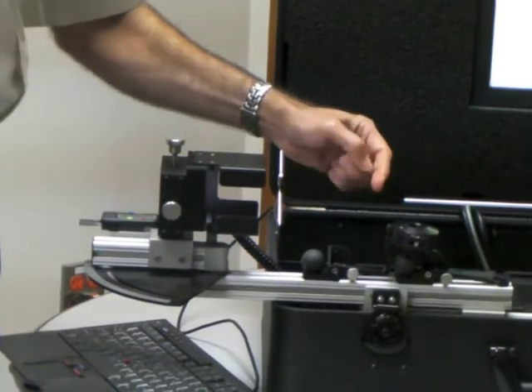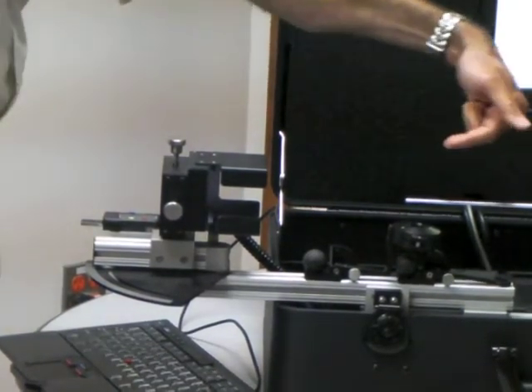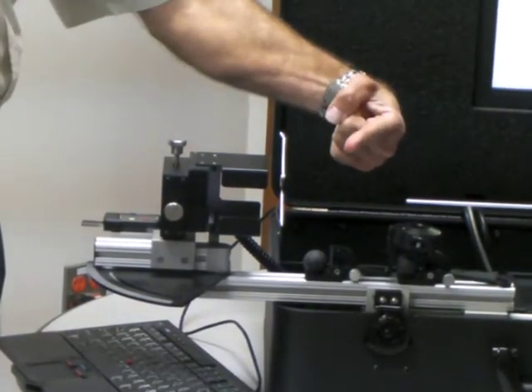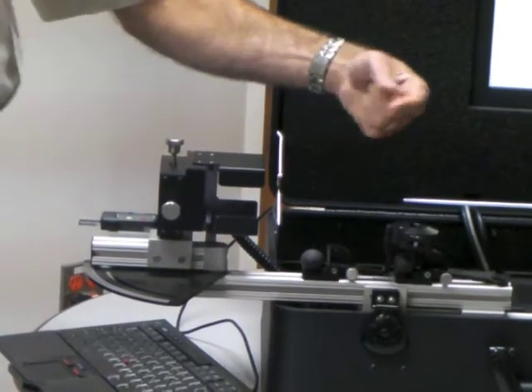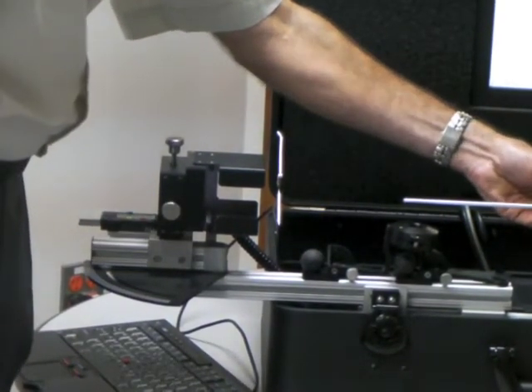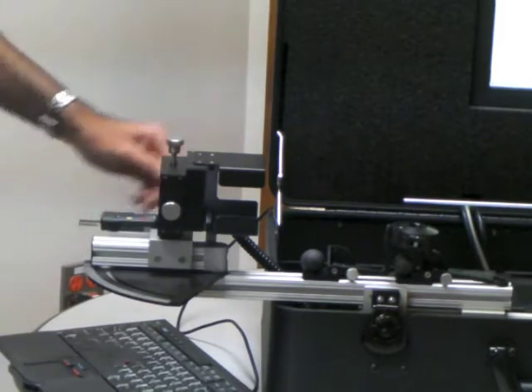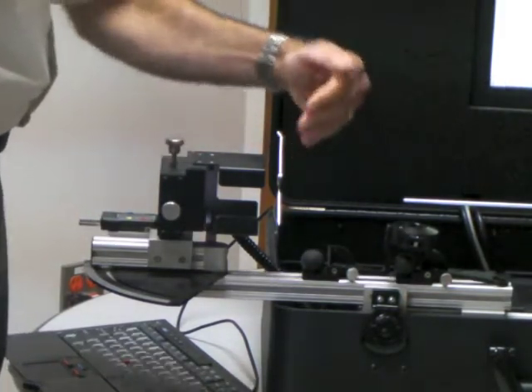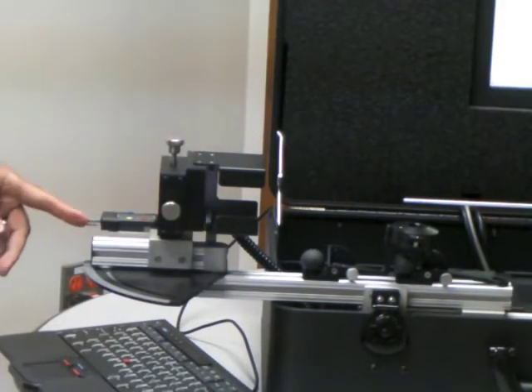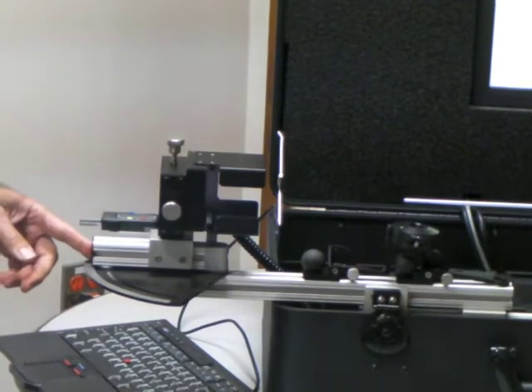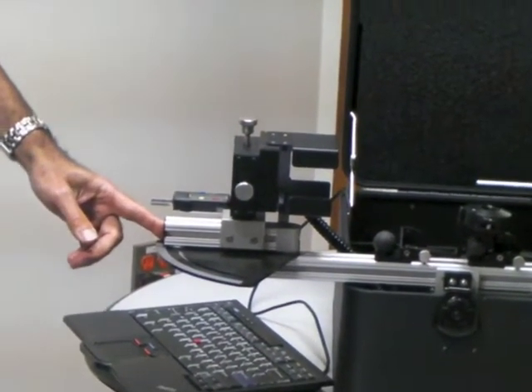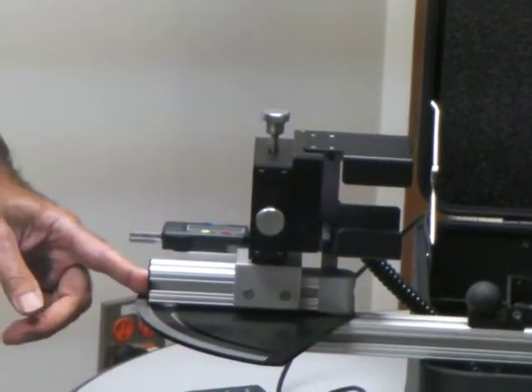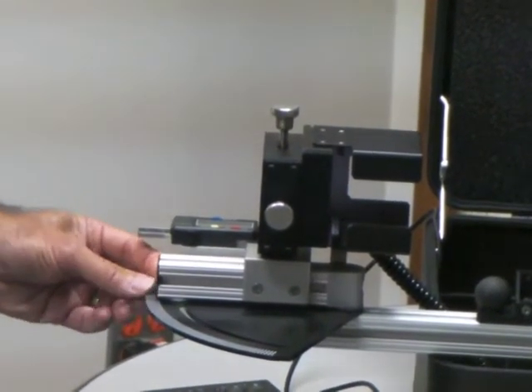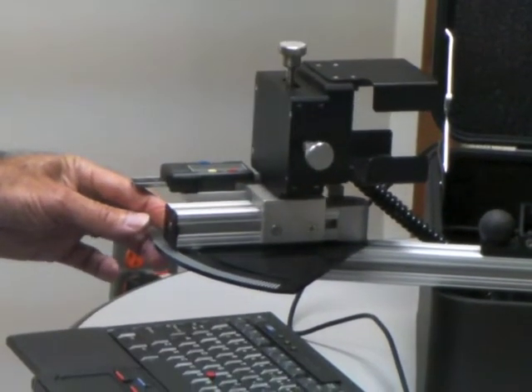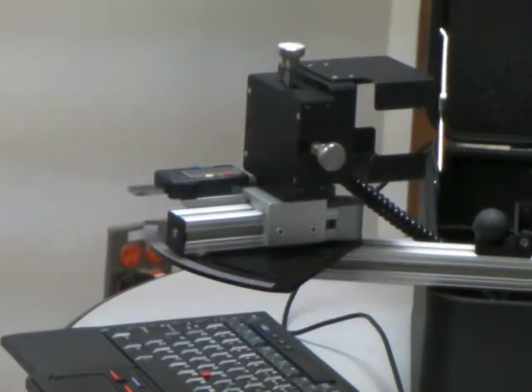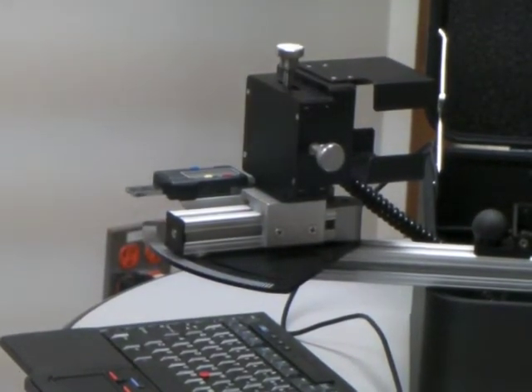So what we want to do is have the direction of view either going straight or coming out from the case. And we'll set this not perfectly, but just approximately. We set it going outside. The next thing we do is we set the angle of the target holder to the nominal direction of view of the scope. This scope is a 30-degree scope, so we'll just rotate this to 30 degrees.